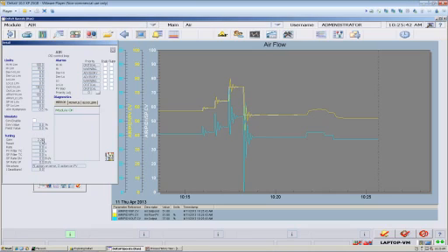In the meantime, I'm choosing a Lambda time of 12 seconds. Now that follows my rules of it's more than 3 times greater than dead time. It's somewhere between 1 times and 3 times my time constant. And I'm going to put in the calculated tuning parameters.